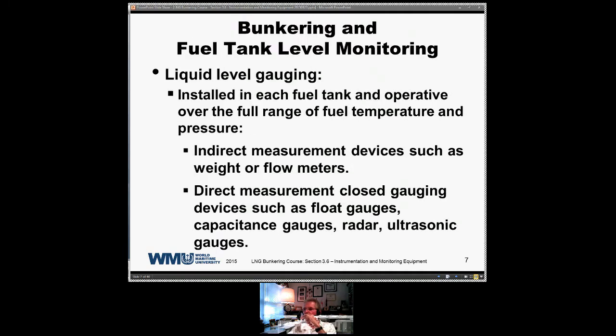Liquid level gauging is installed in each fuel tank, and they operate over the full range of fuel temperature and pressure. There are indirect measurement devices, such as weight and flow meters, and direct measurement gauging devices, such as float gauges, capacitance gauges, radar, and ultrasonic gauges. We're going to concentrate particularly on just the floats, capacitance, radar, and ultrasonic. Flow meters is something I have not seen used with any great frequency. You may find them in loading or discharge terminals, but on board ship you usually do not find flow meters.